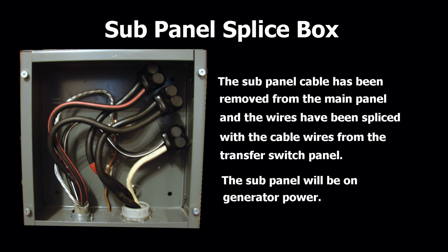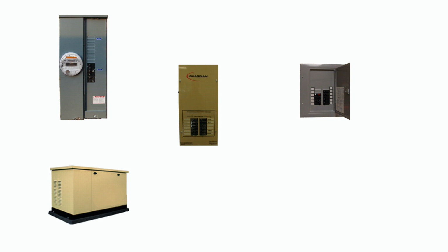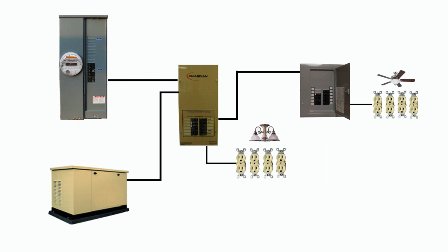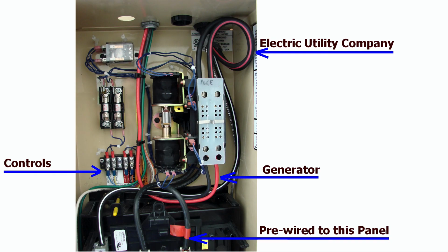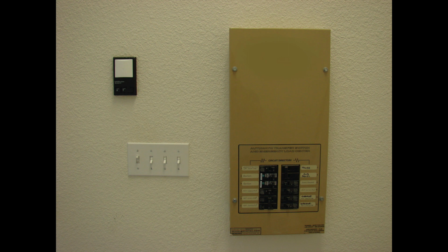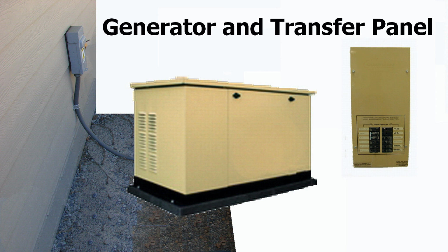There's a circuit breaker in the transfer switch panel that these wires attach to. The connection for the main panel is basically a 2-pole breaker that will be feeding this sub-panel. The 2-pole breaker is sized, in this case, at 100 amps because this sub-panel is a 100 amp rated panel. But again, your limiting factor is the size of the generator. For the most part, when we're on generator, we want lighting and receptacle outlets as needed, especially for the refrigerator.